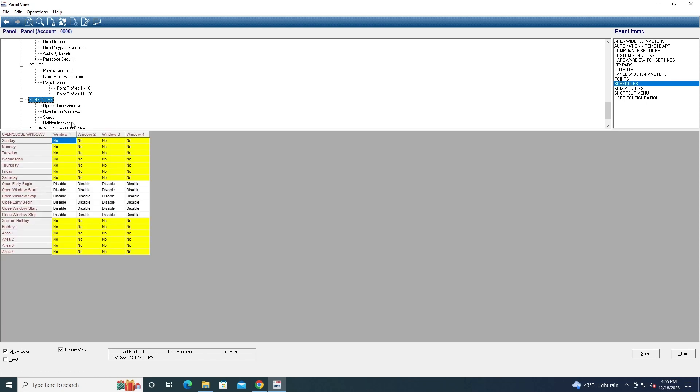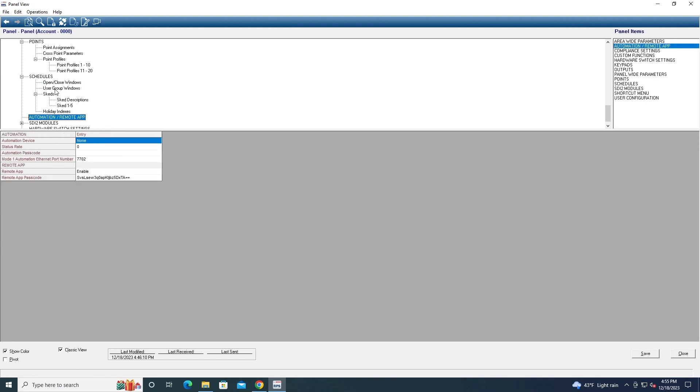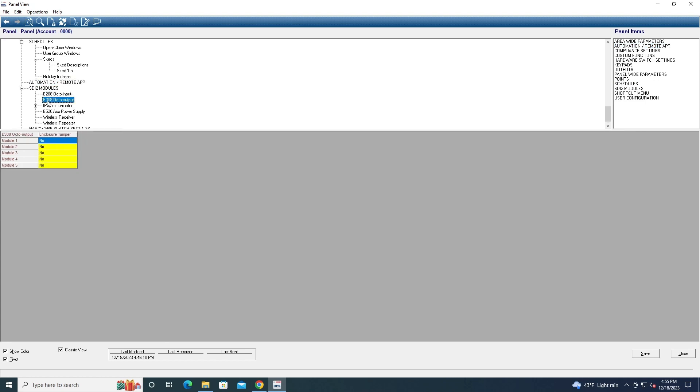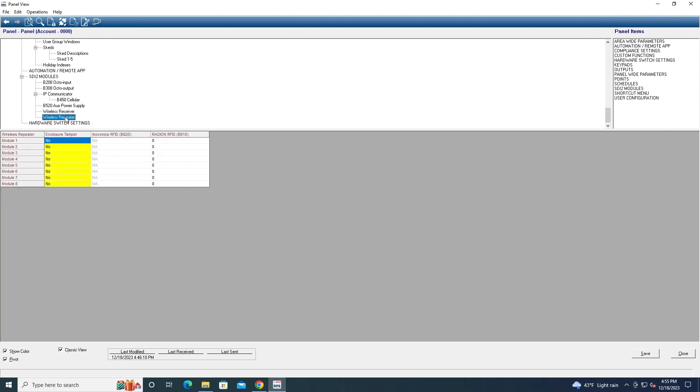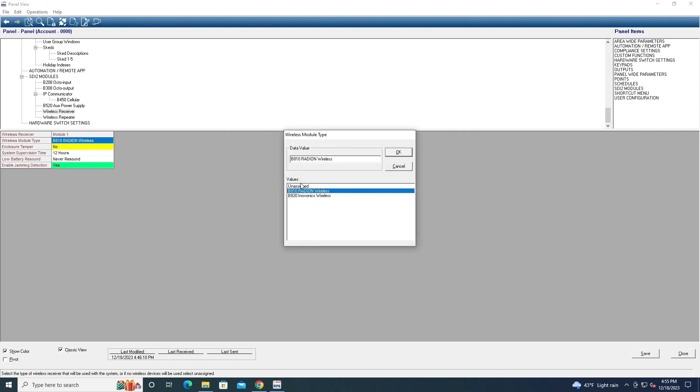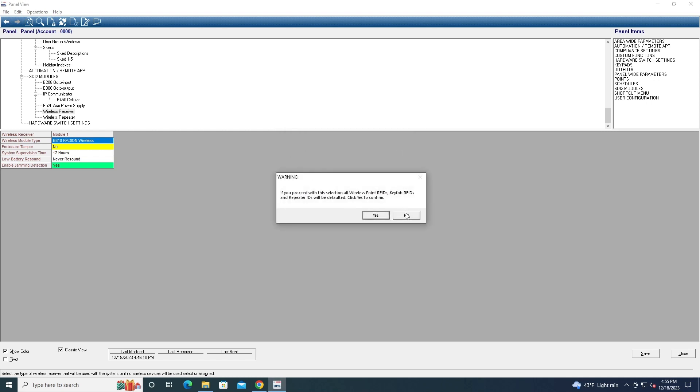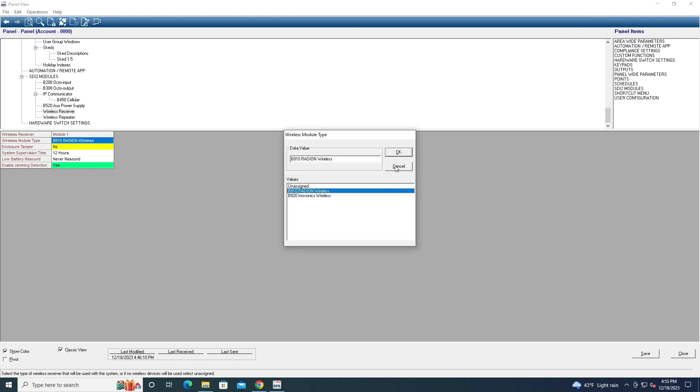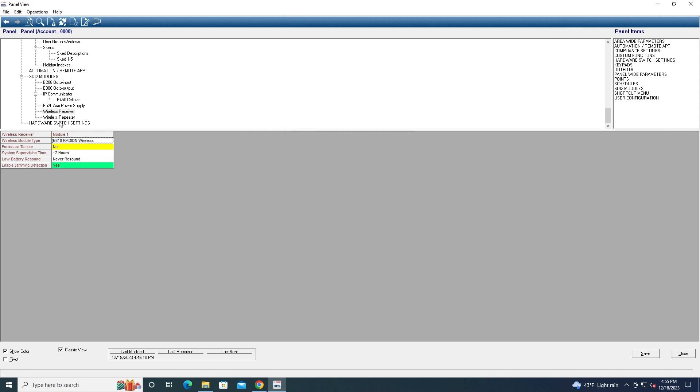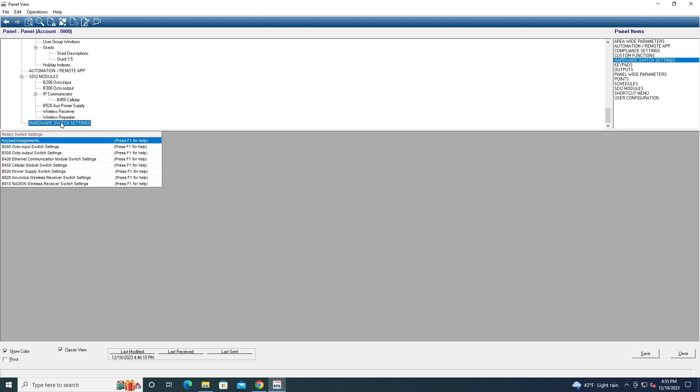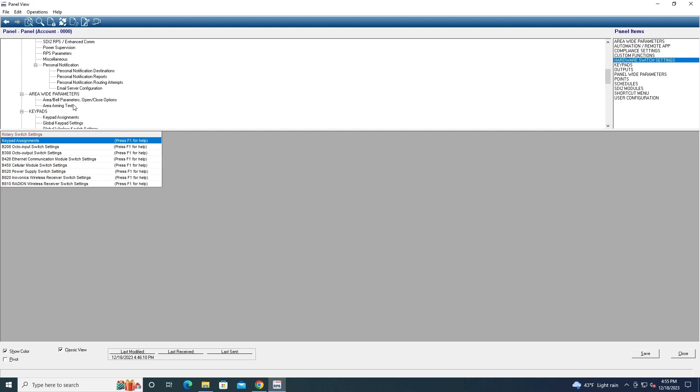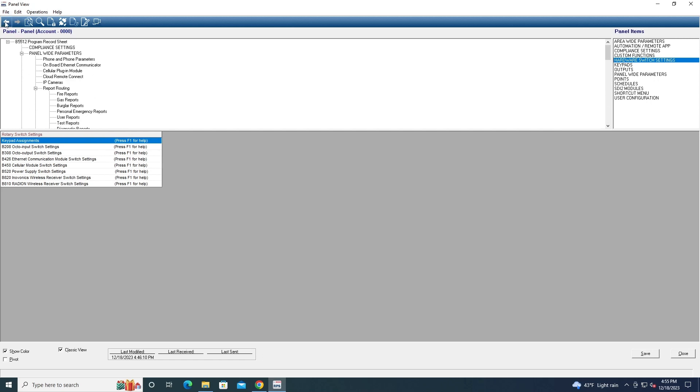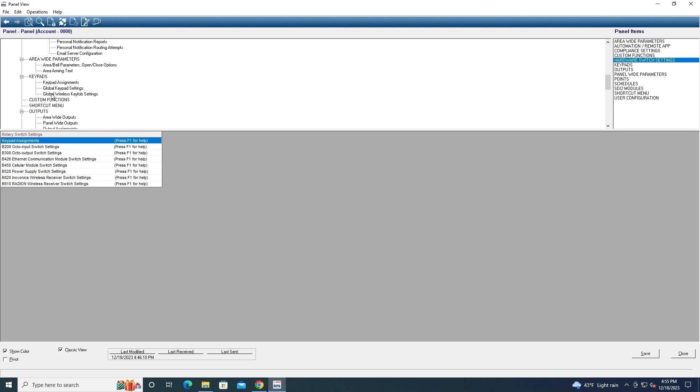You can configure your schedules for your system. And then you got your remote app, your SDI2 modules like the Octo input and output things, the IP communicator, and the wireless receivers. And if you have a wireless receiver, if you don't have a wireless receiver, make sure this is on unassigned or else you'll get a missing wireless device trouble. You can also turn on if you have a cover tamper switch, and here you got your repeaters and your hardware switch settings. So basically for all these settings they have, of course the B9512G will have more settings but it's because they're more complex panel. You have your access control settings and stuff. Also you can set more fire stuff and commercial, obviously it's a commercial panel, obviously you can have more settings on that, but I'm not going to get into that right now.